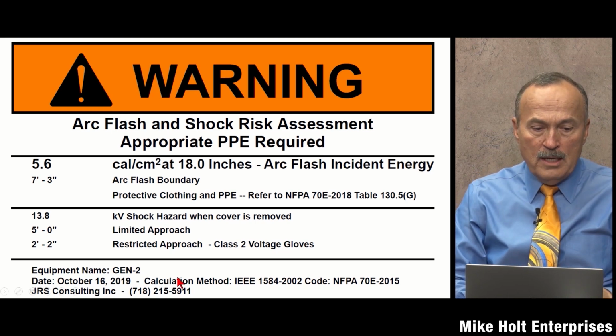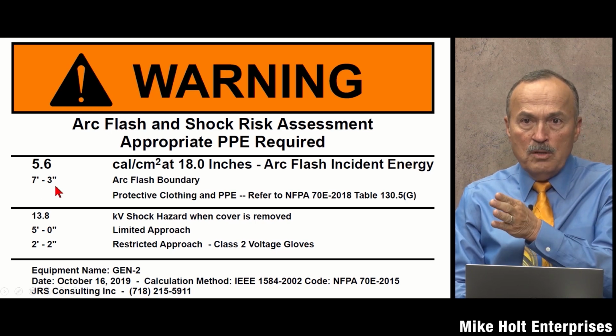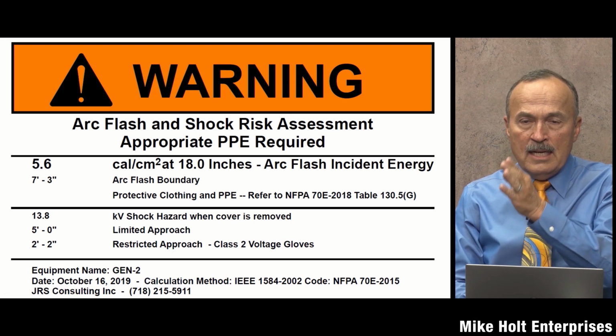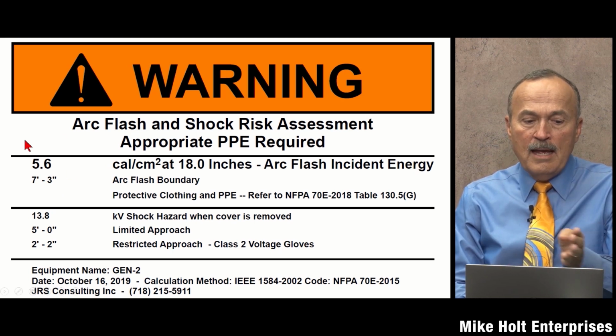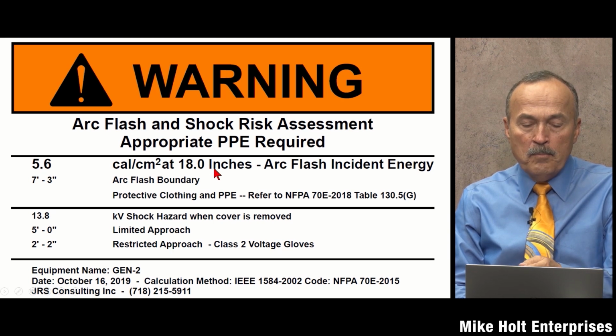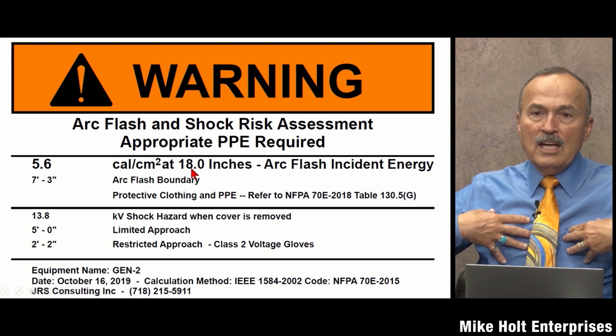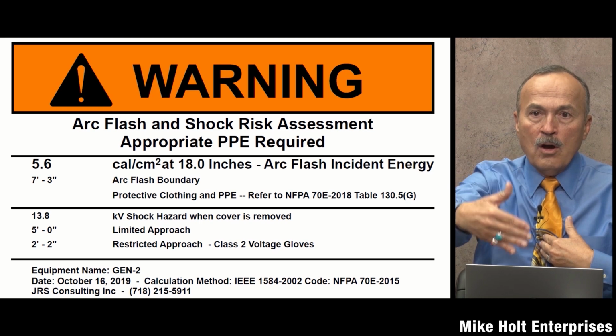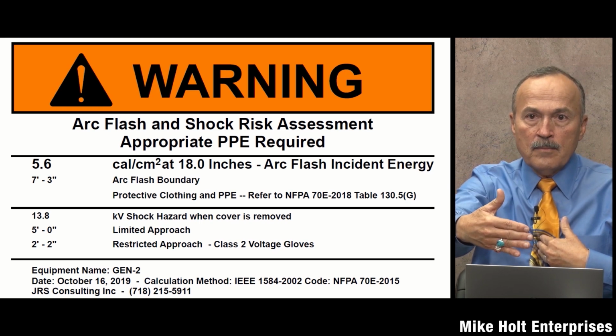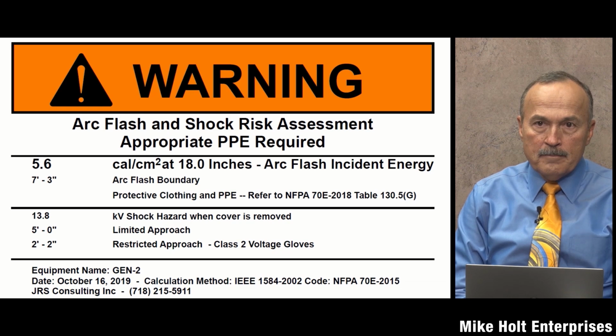And you're saying back over here, the 7 feet 3 inches, that's when you begin the second degree burn. So at that point, we need to have the 5.6 so that your chest is 18 inches away from the arc flash event. Right. Walking in there, of course, the closer you get, the higher the burn is going to be. So walking into that area at 7 foot 3, that's the onset of second degree burns. That's where we would demarcate our area in order to ensure that people who are unqualified and not dressed appropriately would not be exposed to that level of energy.